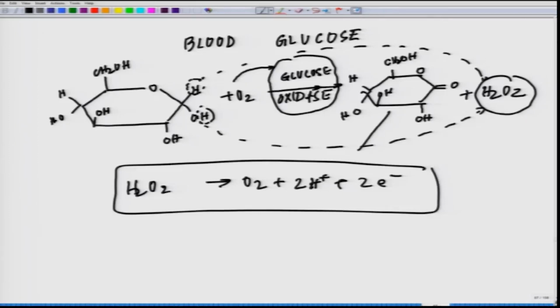The glucose monitor's response is dependent on the concentration of the oxygen in the enzyme layer. So, this oxygen has to be on top of this enzyme layer. But if the oxygen concentration is low, the system will show as if there is low glucose. So, you are totally dependent on oxygen for this reaction to happen. Now, one way out is that oxygen is nothing but an electron acceptor. If in some way you can substitute oxygen with something else, another mediator.